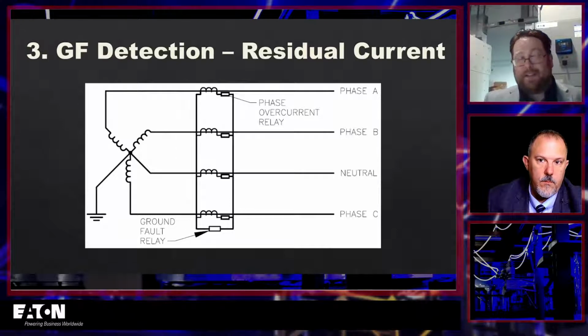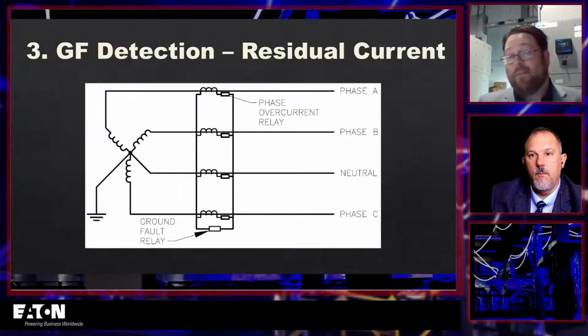The zero sequence is one CT. So think about the magnetic fields of all those wires. Magnetically, they cancel out, so you don't get any magnetic field in the iron core of the CT, which would then go over to the secondary wires. Versus residual, every wire is going to have that magnetic flux going through the CT. It's going to have secondary current, and then we sum the secondary current. Same principle, just a different way of measuring it.